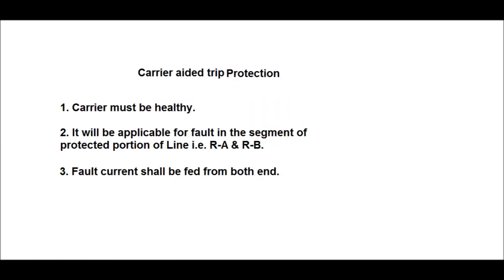What are the necessary requirements for carrier aided protection trip? The first requirement is that the carrier channel must be healthy. It must be optical fiber cable, or earlier a power line carrier frequency was used. Number two, it is applicable for a fault in the protected segment of the line. That is, if a fault occurs between A and B, fine; if the fault occurs beyond B, the carrier protection logic is not possible.